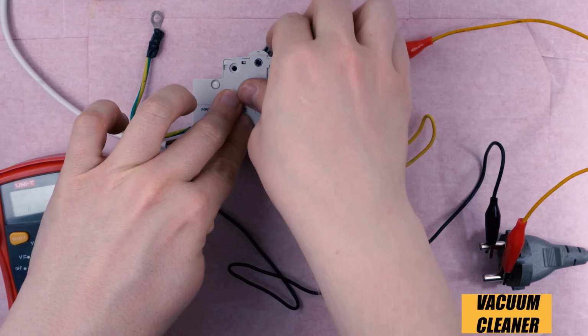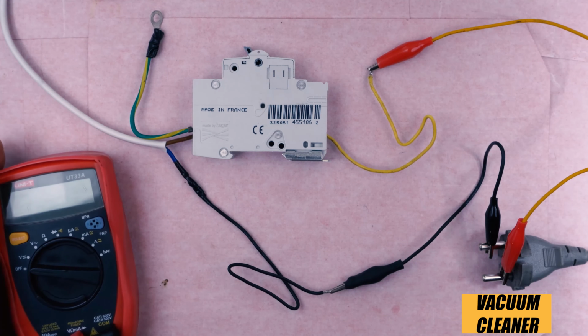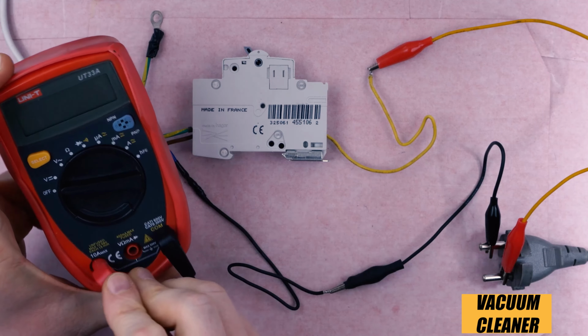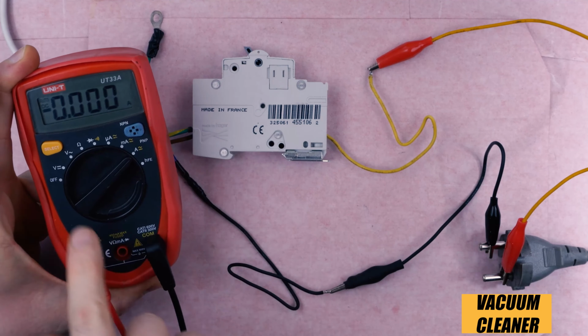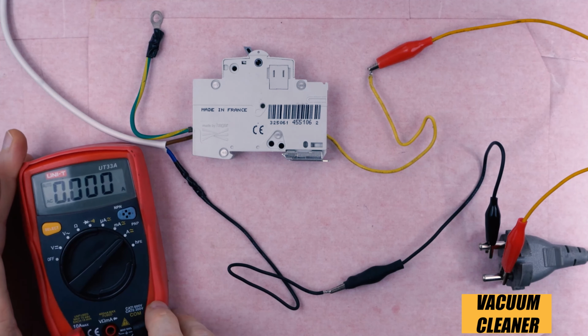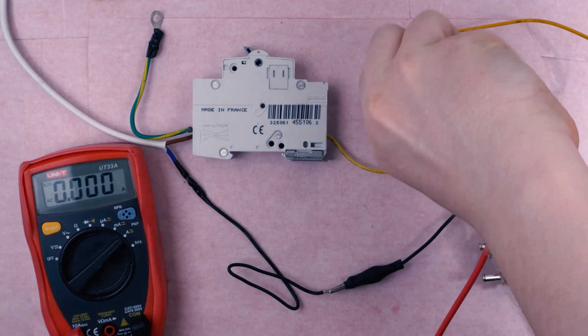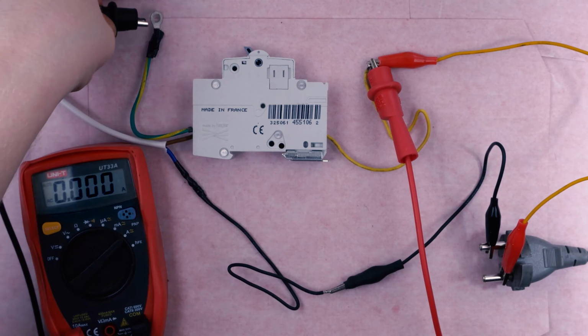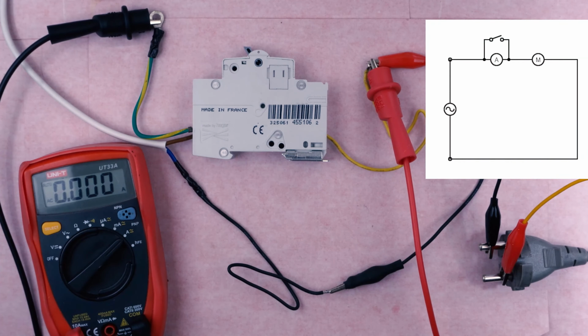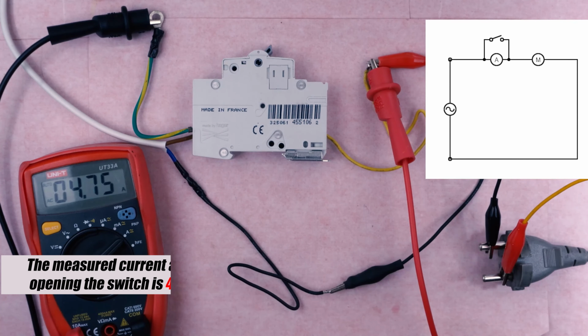In case you need to measure current of an electric motor, especially if it's a fridge or an air conditioner compressor, you have to keep in mind that their inrush current may be significantly larger than their normal working current. So, if you try to use your DMM to measure it, the inrush can kill the shunt. So, here's a life hack that will allow you to make this measurement and keep your multimeter safe. Wire your DMM, like usual, in series with the motor. Attach a switch in parallel with DMM and close it. Start the motor and wait for it to pick up speed. Now, open the switch and have your measurement.